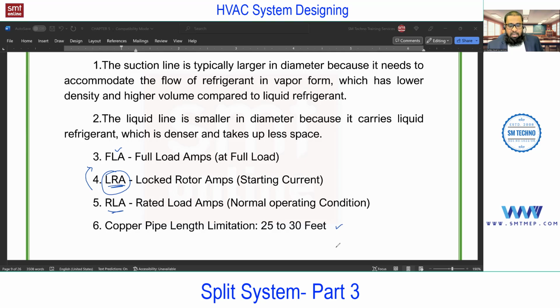Next, one more important point: the copper pipe length limitation with almost all manufacturers, except some high class, is in between 25 to 30 in general. Again, this length will vary as per the position of the indoor and outdoor. For example, consider a building. Suppose I place the outdoor on the top and the indoor here. This is one case. The second case, for example, the outdoor at the bottom, on the ground, connected to the indoor. Or in the third case, the outdoor is on the top and the indoor at the bottom. So this copper pipe length also varies as per the position of indoor and outdoor.